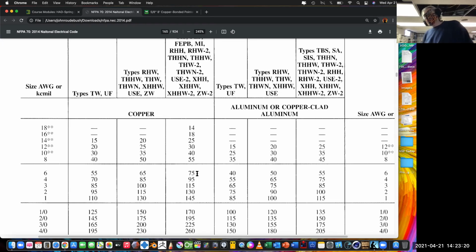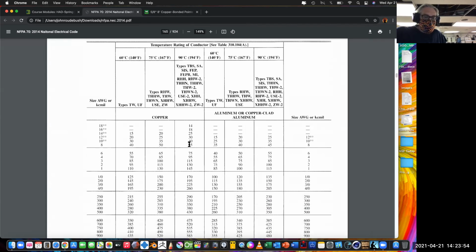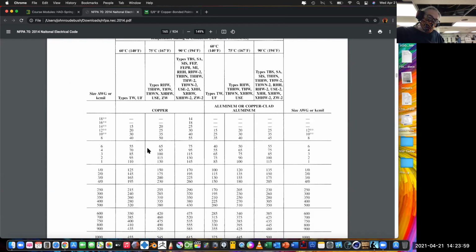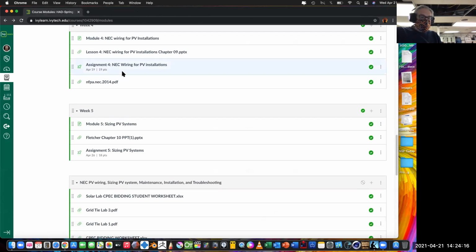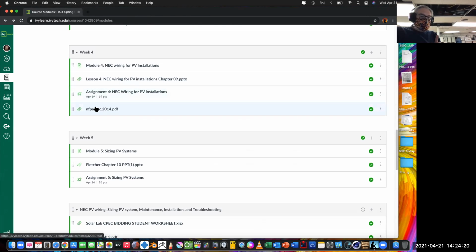So when we're talking about whether it needs 3 or more hours of protection, yes, you put the 1.25 in, but that's if it's at 75 amps or 60 amps for 3 hours straight. These can do that, but as we've seen, they're going up and down as the day goes by, so they'll be lucky to have 60 amps on them for 3 hours straight. So the wire's never even getting that hot. But you have to think about that. That is where we get the size of the wire for our system, and that is the logic behind it. I know we have those little charts we were working on, because there's more to it than that. We've got our surge capacity, we've got our ambient temperature correction factors. We have all that stuff we have to take into consideration. And that's how you find that in the code book.